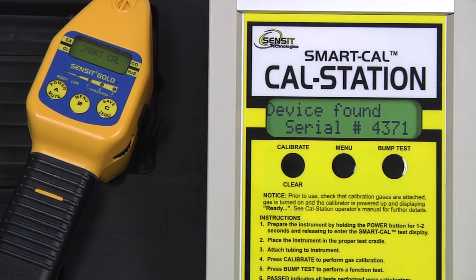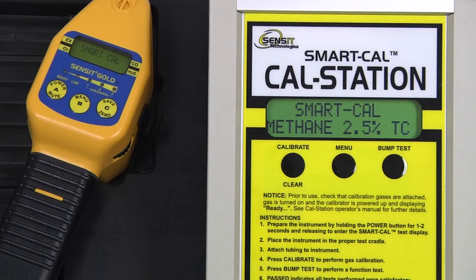The instrument has been found. There will be a flow check, followed by a 60-second purge. After the purge is complete, the instrument will auto-zero and the calibration process will begin. In this case, 50% LEL methane is the first gas. The TC sensor, internal on the instrument, will be calibrated first, followed by the 2611 or LEL sensor at the end of the gooseneck.